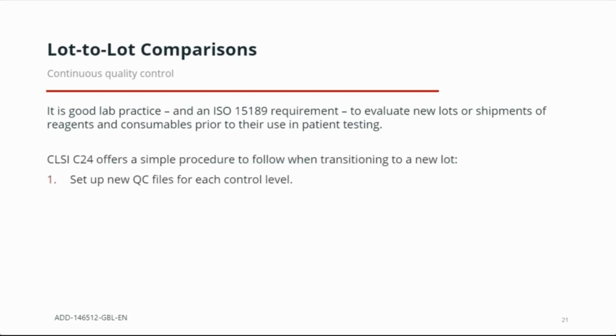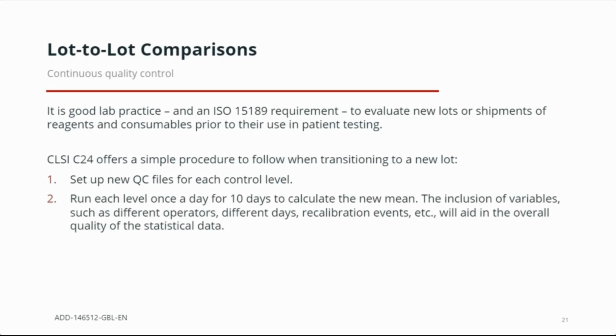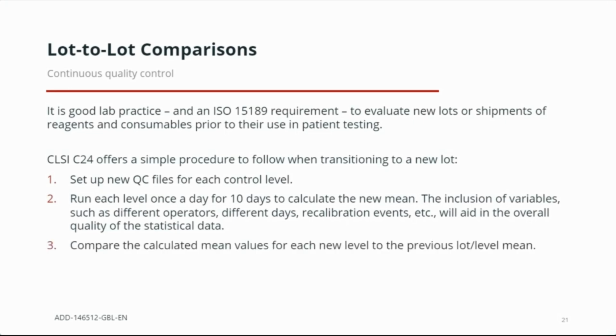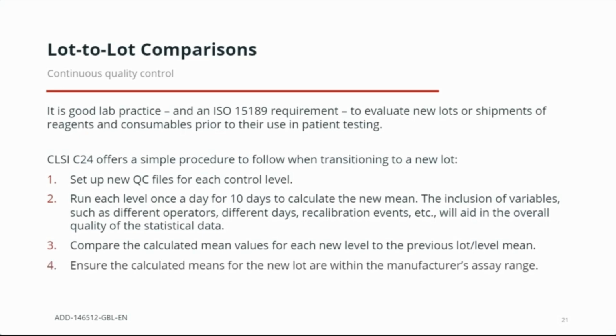So CLSI C24 offers a simple procedure to follow when transitioning to a new lot, beginning with setting up new QC files for each control level. So we're analyzing the current existing lot and the new lot side by side. You run each level once a day for 10 days to calculate that new lot mean. That includes, again, variables we've described before, different operators, different days, perhaps recalibration events, as much information and influences as possible to aid in the overall quality of our statistical data. We then compare those calculated mean values for each level to the prior lot means, and then we ensure that those means for the new lot are within the manufacturer's assay range.